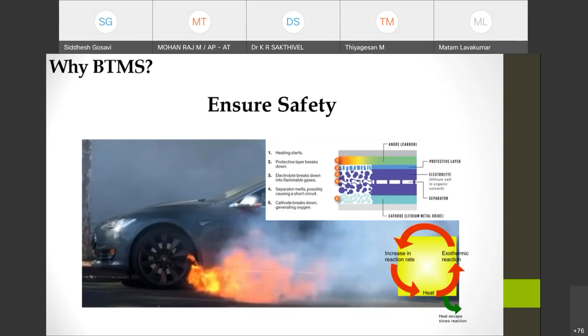So to summarize, what the BTMS shall do is make sure that your battery temperature does not reach above 50 degrees Celsius, and that it does not reach below 15 to 20 degrees Celsius. In case it reaches, or predicts it is reaching, those limits, it shall take the necessary steps to avoid any casualties. So that is another major reason to use the BTMS system.